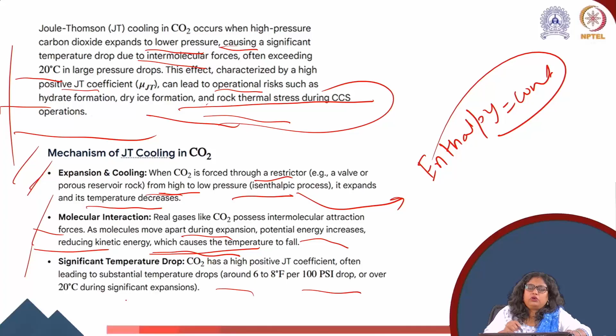Then molecular interaction. CO2 does not behave as an ideal gas; it behaves as a real gas. Real gases like CO2 possess intermolecular attraction forces, and as molecules move apart during expansion, potential energy increases and kinetic energy is reduced, because the total energy has to be kept constant, the conservation of energy concept, which causes the temperature to fall. Now, significant temperature drop: CO2 has a positive JT coefficient, often leading to a substantial temperature drop of around 6 to 8 degrees Fahrenheit per 100 psi pressure drop, or over 20 degrees centigrade during significant expansion. So this is the mechanism of JT cooling in CO2.